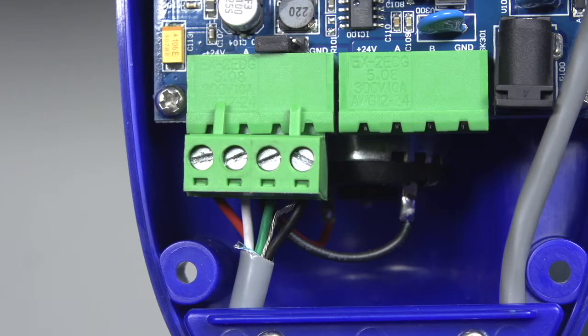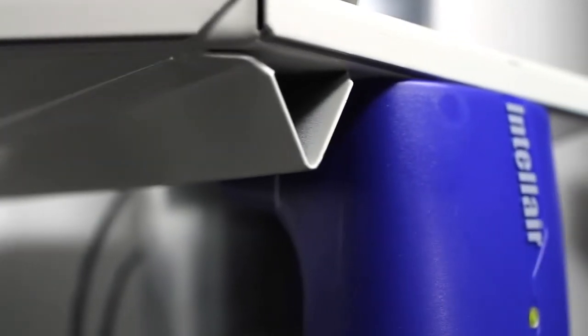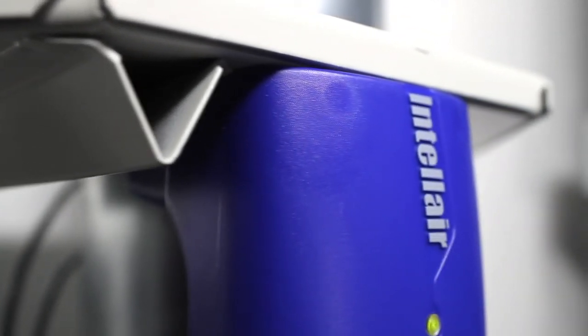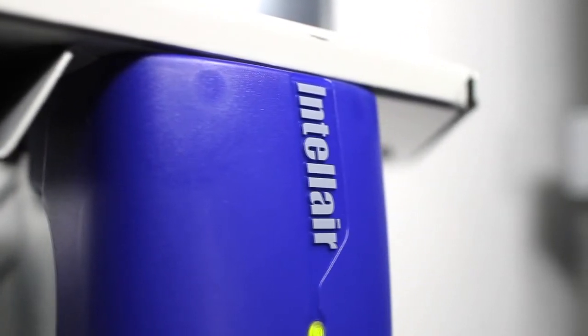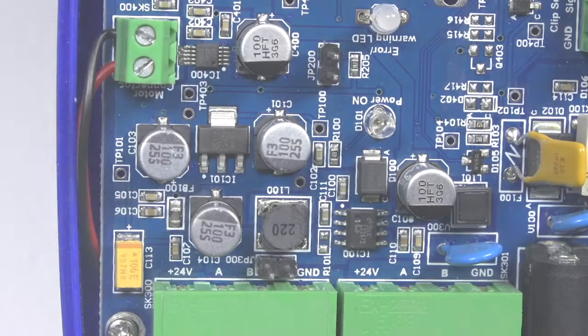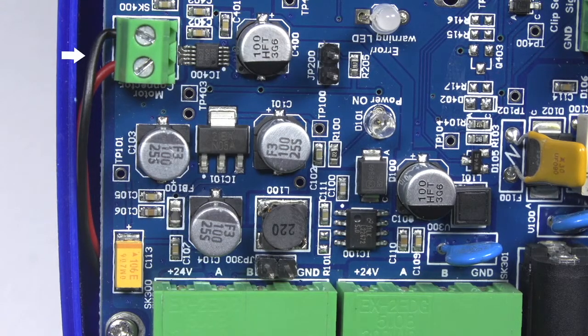If a communications error occurs, ensure connections are made properly and that shielded cable is being used and is grounded accordingly. If an overcurrent error arises or a damper doesn't open or close after a maximum timeout period, check to ensure the damper blade passage is not obstructed and moves freely. When the motor not connected message appears, ensure that connections are made properly.